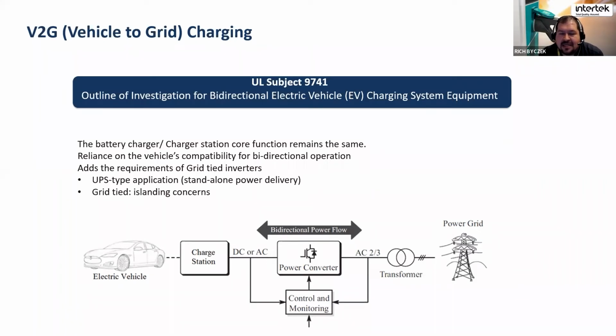We have what we call anti-islanding concerns: if there's a power outage and you're powering your home in an emergency through the vehicle, you want to ensure you're not sending electricity back to the transformer that feeds your building. That's a safety risk for line workers on the grid side. So you have to demonstrate either that this infrastructure has no direct connection that could feed energy back to the grid, or that you prevent that energy transfer when the grid is down. Very similar to GFCI circuits, you have to demonstrate the ability to create those safety situations, regardless of how you do it.